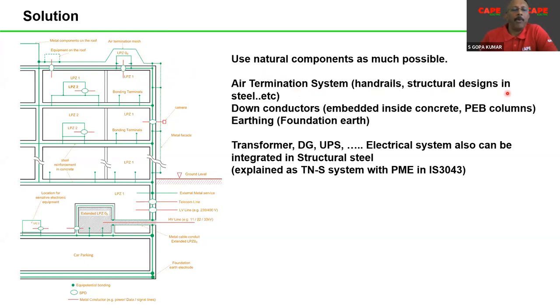Structural designs: a lot of buildings have structural designs, like some architectural design steel materials at the top of the building. We are sometimes forced to keep a rod over and above this structural design, which is practically not required. If your structural design is a steel material, that steel material can work as air termination. A small paint above the steel material you can ignore, which is also written in the standard. This small thickness of the paint, we can ignore it. Basically, the structural design material, you can see if you look at the high-rise buildings, most of them have something at the top with some kind of design for aesthetics. So those materials, if they are made of steel, can be used as air termination.